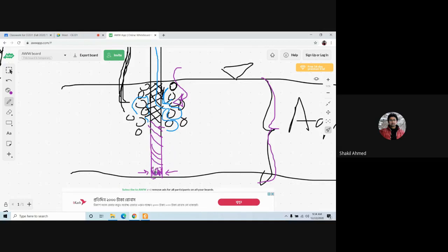So, for example, in 20 or 30 years of design life, maybe the deposition height will be this. So what we do at the beginning is we give a solid pipe here. We don't give a screen at the bottom. So this is a solid pipe. Whatever material enters here gets deposited here.